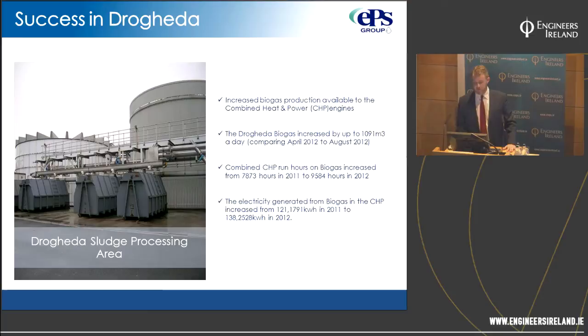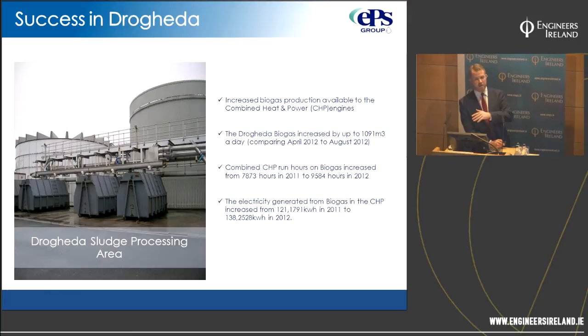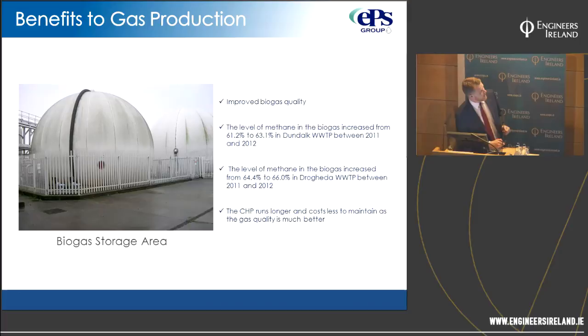There's been an increase of nearly a third in CHP run hours — and any run hours in a combined heat and power engine mean we're producing electricity on site for our own use. The electricity figure looks a bit low comparing 2011 to 2012 because we only turned Drogheda on in June. However, across Drogheda and Dundalk combined it's a 22% increase in kilowatt hours generated on site — about 28% on Drogheda alone.